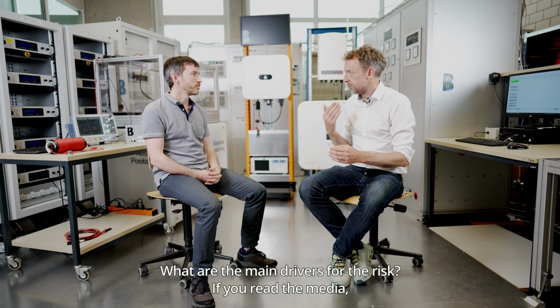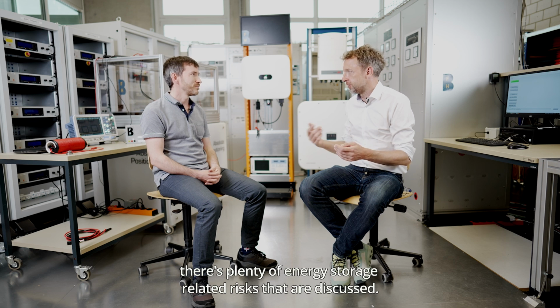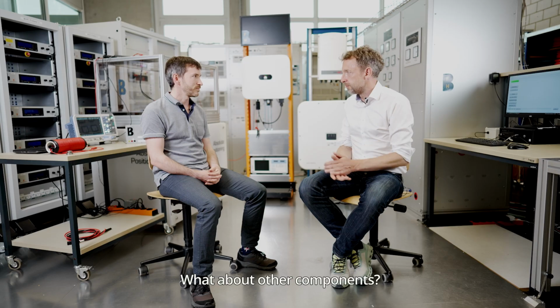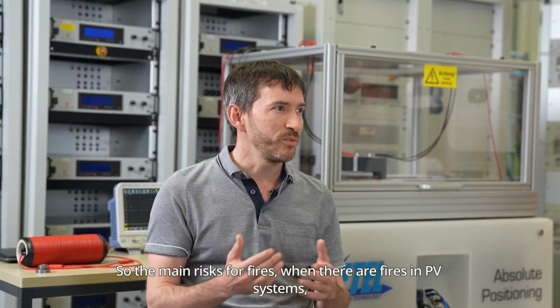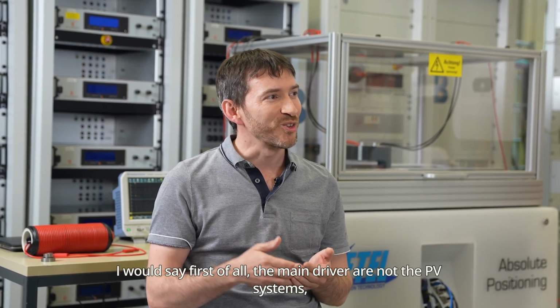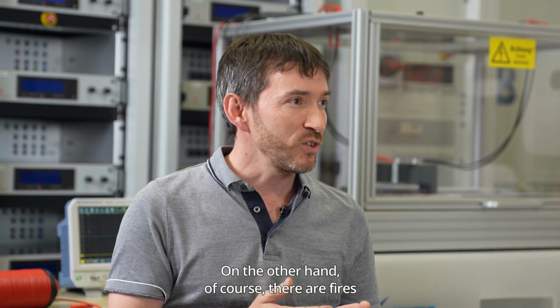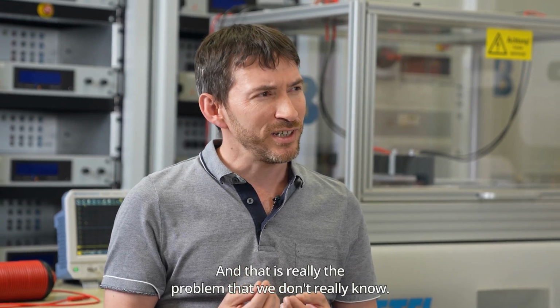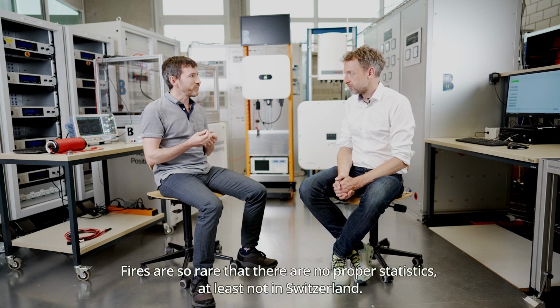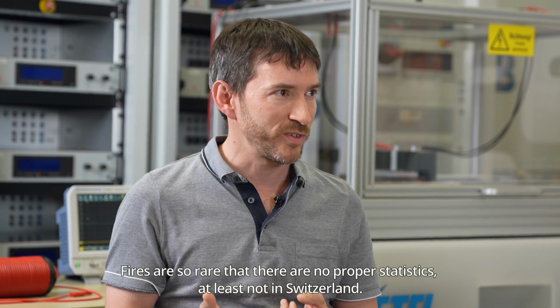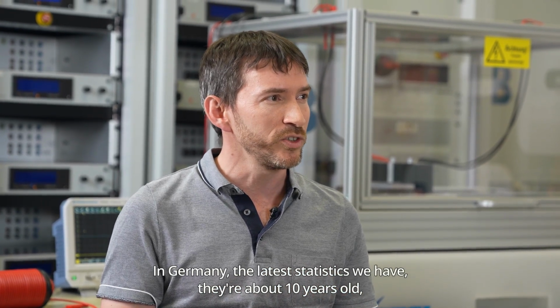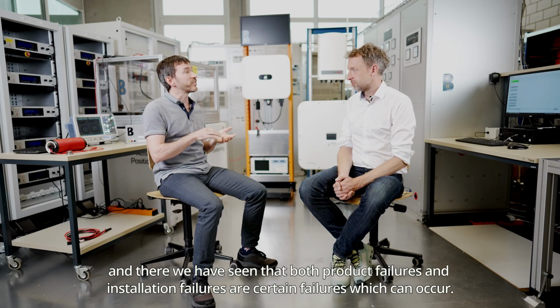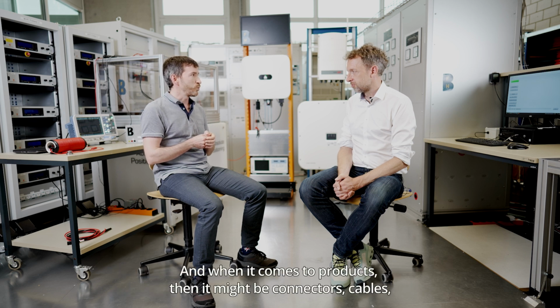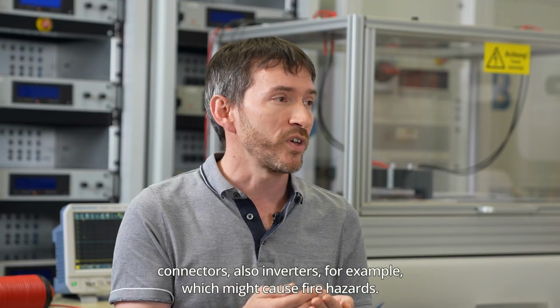What are the main drivers for the risk? If you read the media, there are plenty of energy storage related risks discussed. What about other components? When there are fires in PV systems, the main drivers are not the PV systems, but fires in buildings where there is a PV system on the rooftop. On the other hand, there are fires which were caused by PV systems, and there's the problem that we don't really know. Fires are so rare that there are no proper statistics, at least not in Switzerland. In Germany, the latest statistics are about 10 years old, and there we have seen that both product failures and installation failures can occur. When it comes to products, it might be connectors, cables, also inverters, which might cause fire hazards.